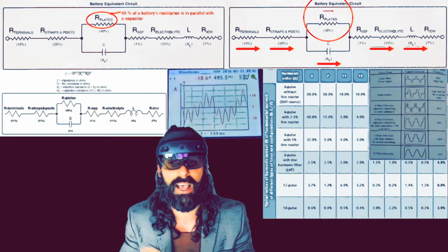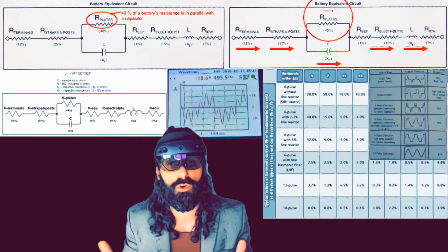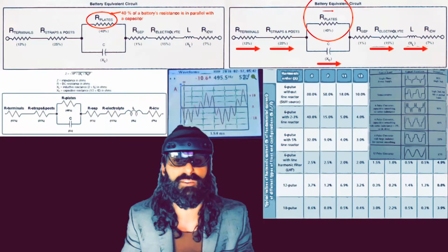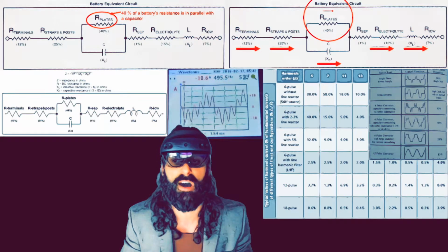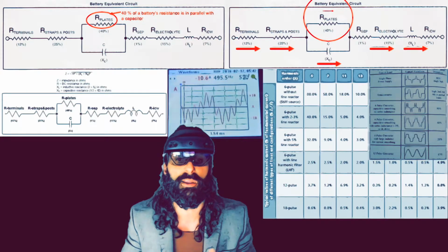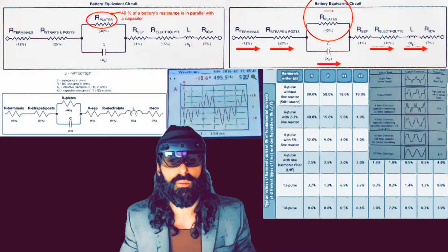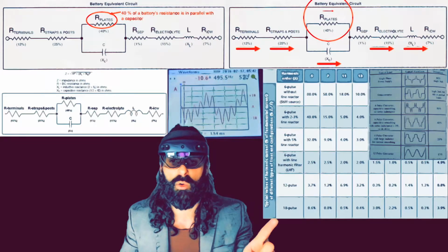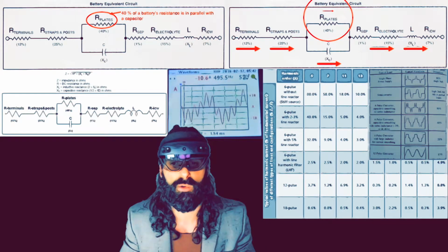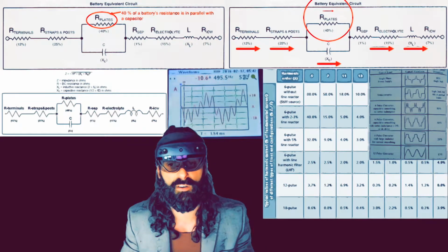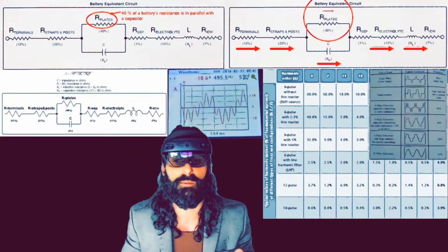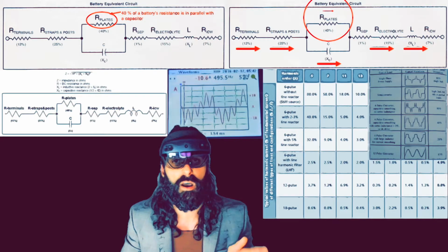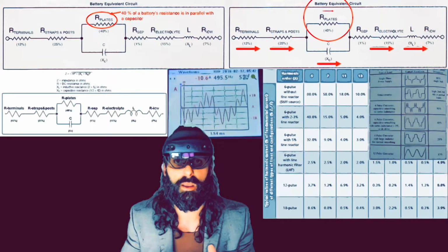Now the conductance test applies a specified AC voltage signal that is capacitively coupled to the battery, and the resulting AC current is measured, calculated as 1 divided by E divided by I, or simply C equals I divided by E. I want to go over some of the formulas very quickly. Inductive reactance is 2 pi times the frequency of the device times inductance, in ohms, and capacitive reactance is 1 divided by 2 pi times F times C, where F is the frequency of the testing device and C is the capacitance of the battery in farads, right?